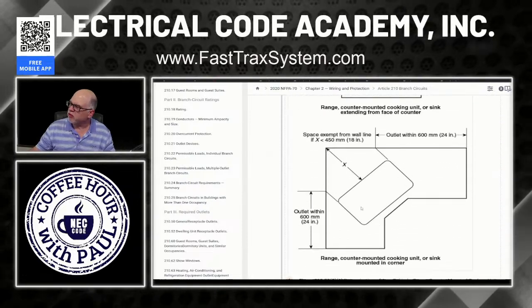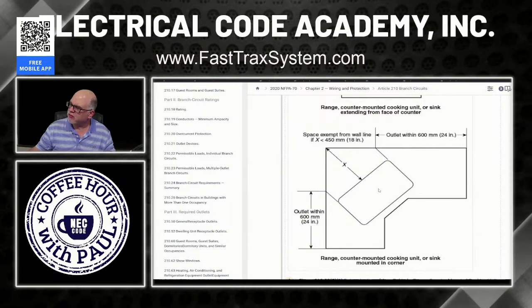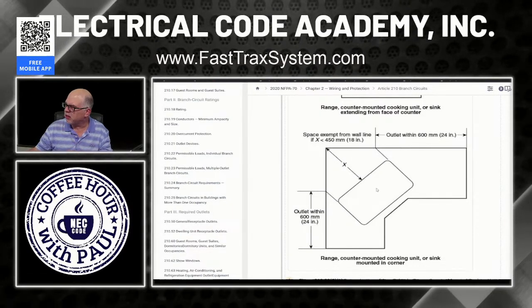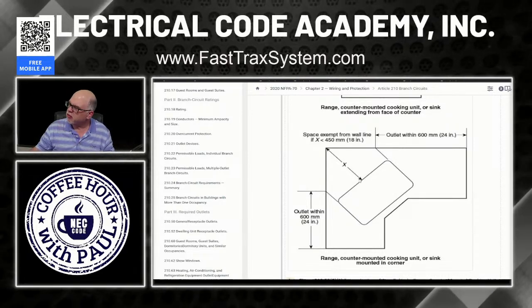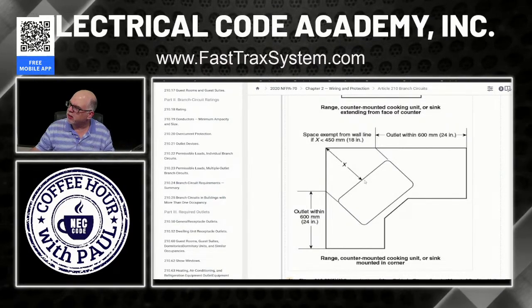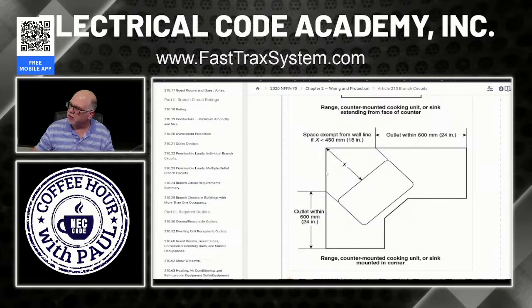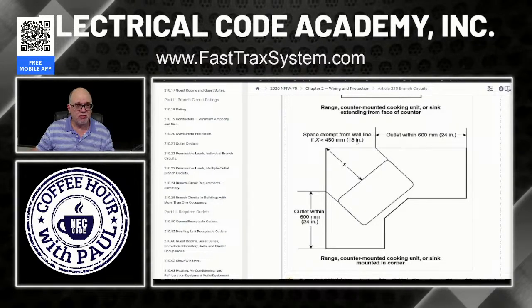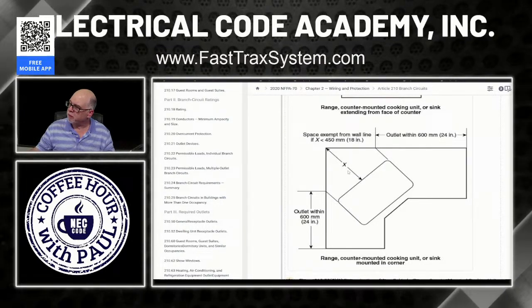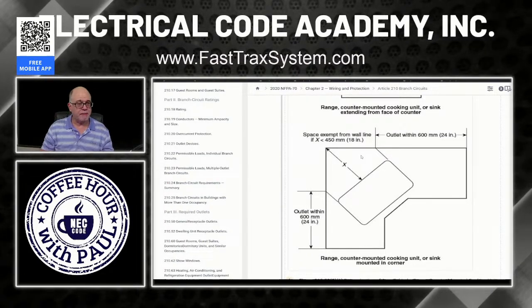Now, what about this one? So this is the one that's talking about the corner. In this one right here, if this is a sink, a cooking unit, or range or whatever it is built in, then the measurement behind it to the corner, this space, is exempt from being considered wall space. All of this is exempt if it is less than 18 inches. So if this space right here is less than 18 inches, then I can forget it even exists.